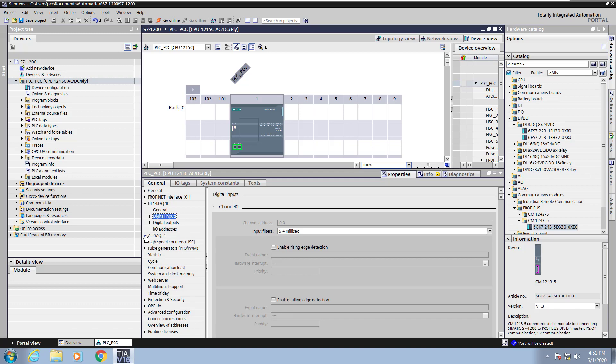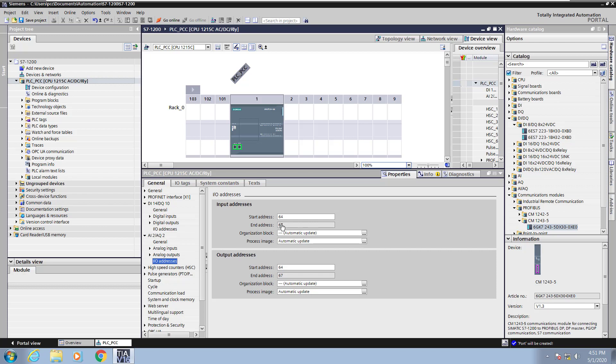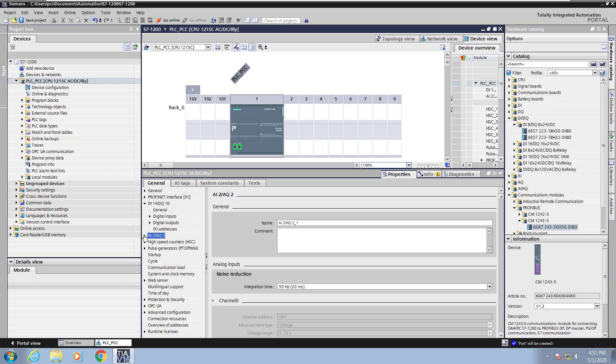Next I'm going to look at the analog input area and expand that out and go down to the I/O addresses area. Here you can set the starting address for the analog inputs and the starting address for the analog outputs. Each analog address would take up two bytes. I'm going to minimize the analog input area.